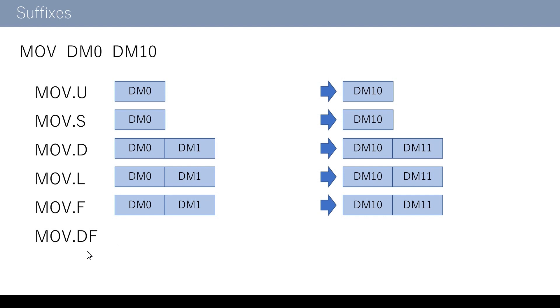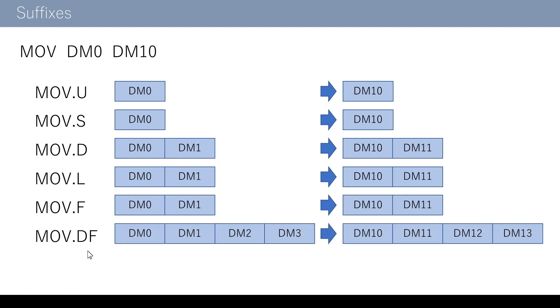Finally, move.df is a suffix for a double precision floating point type occupying four words. Therefore, four words from DM0 to DM3 are copied to four words from DM10 to DM13. As you can see, the range of occupied devices varies depending on the trailing suffix of move.